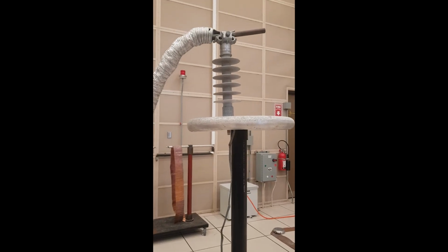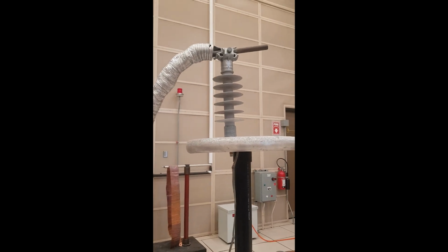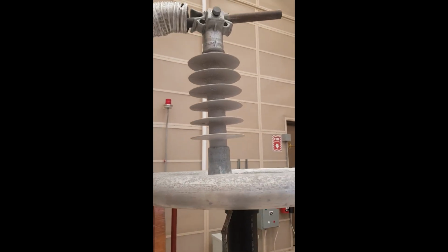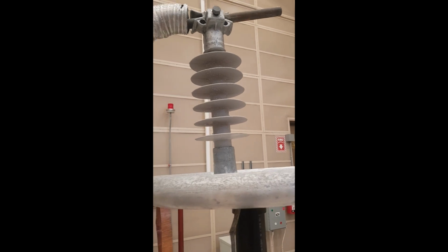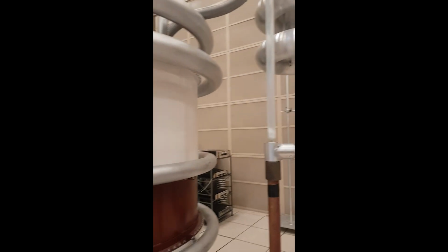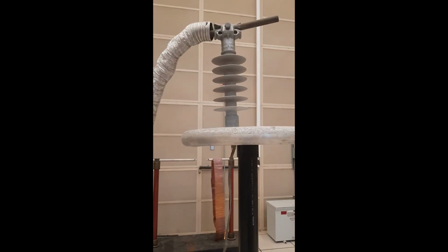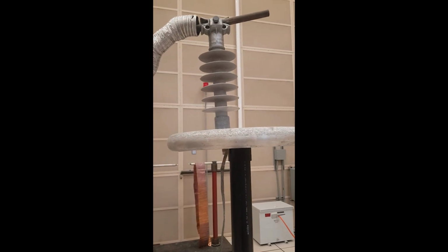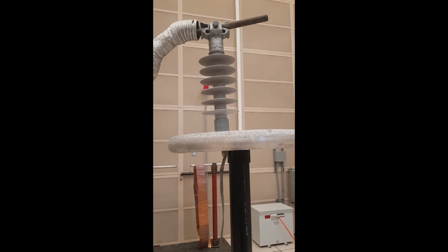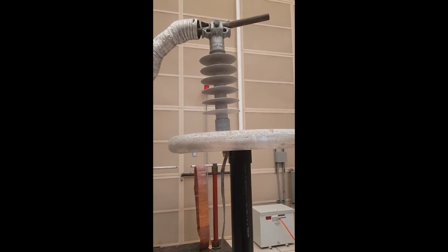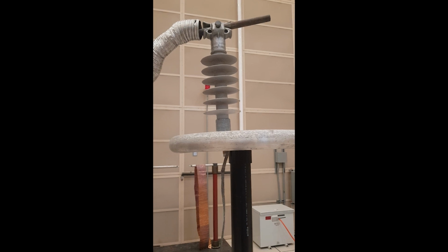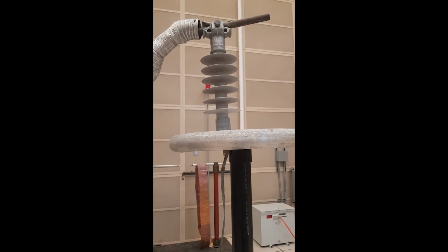This is the setup that we will now be testing. This is basically polymeric insulators. It's wet, okay, and it's connected to a high voltage transformer. So basically now we will energize this insulator, and we will try to measure the dry band arcing using three different sensors: the IR camera, RF antenna, and ultrasonic sensor. Now you can start to hear the dry band arcing on the surface of the insulator.